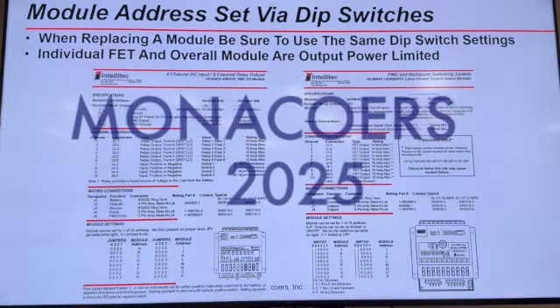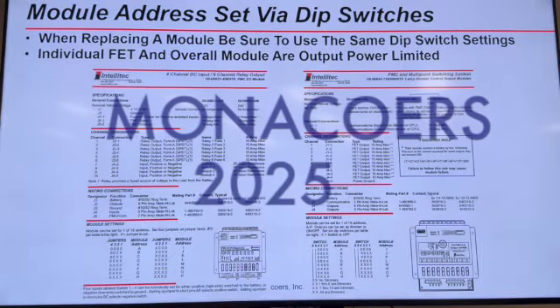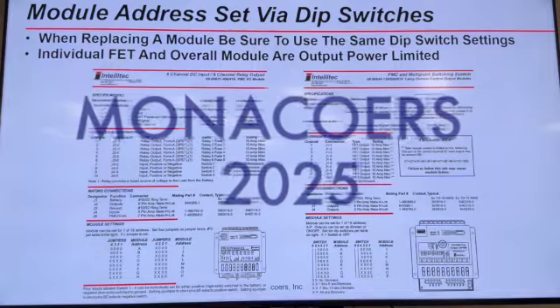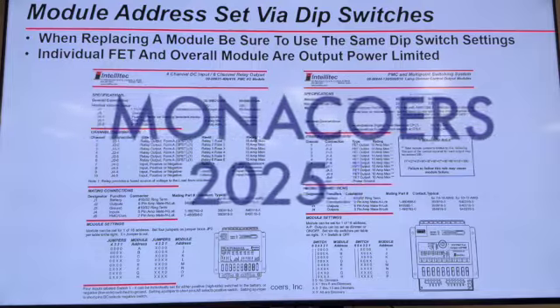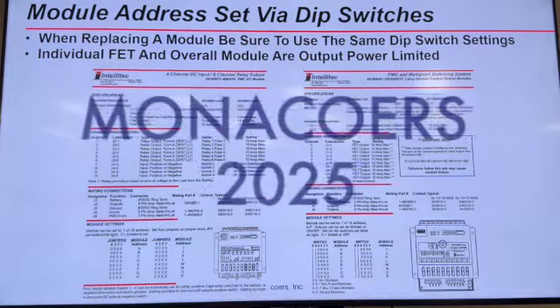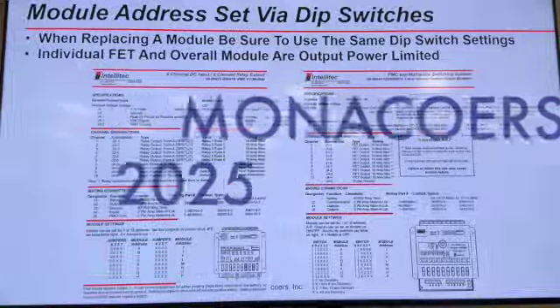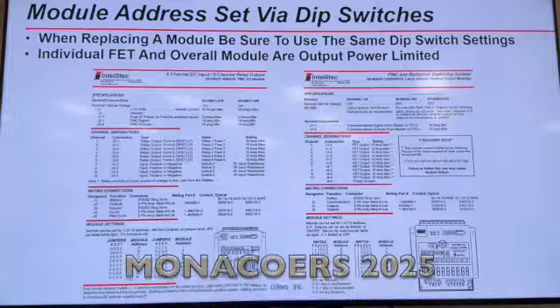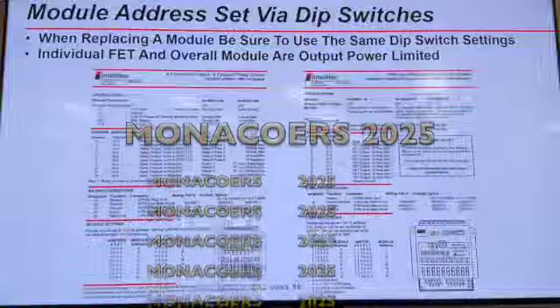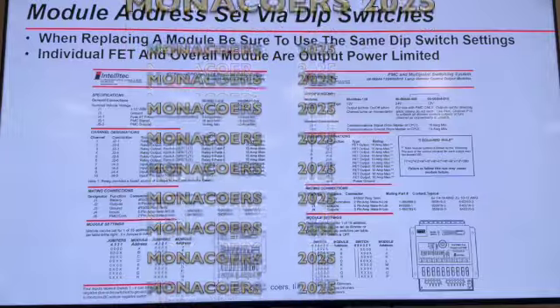Modules address set via dip switches. There are on each one of those modules a series of dip switches that decide whether this is module A, B, C, D, E, F, and so on. If you replace a module, even though it's exactly the same looking module, you have to make sure the dip switch is set correctly, otherwise it will not work.